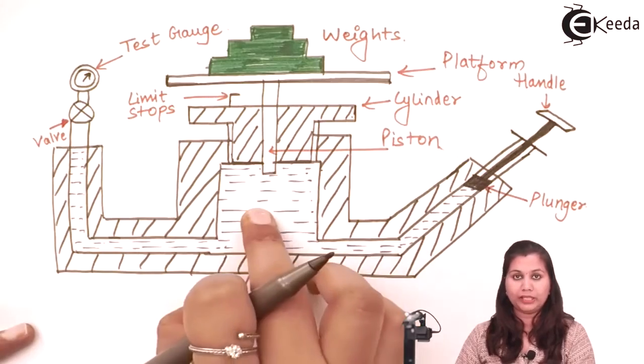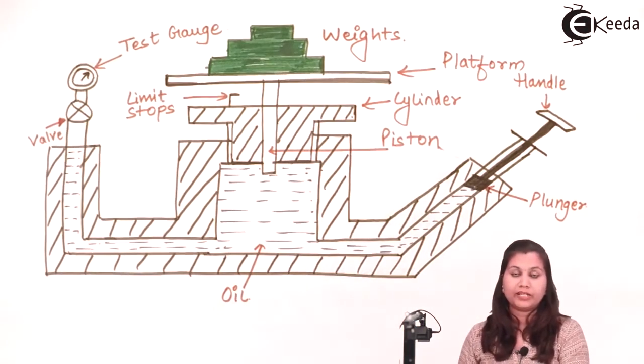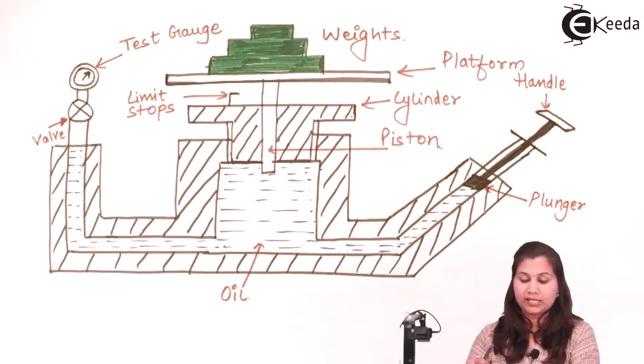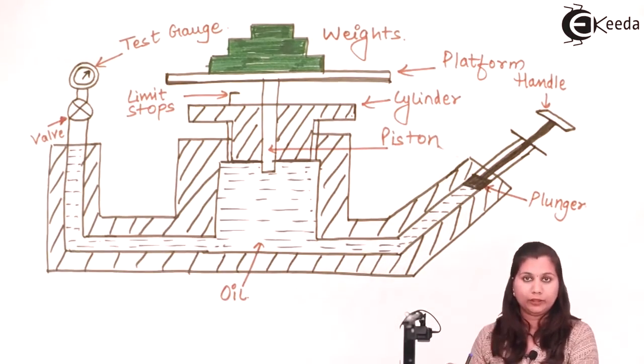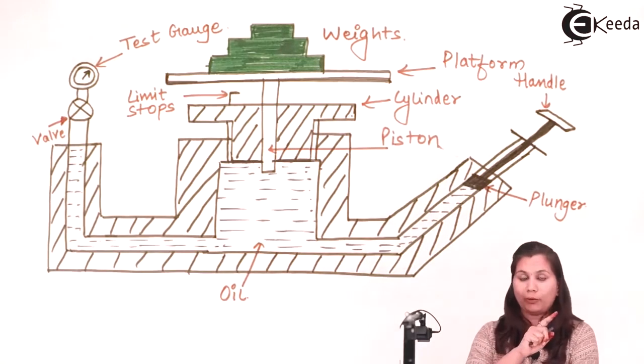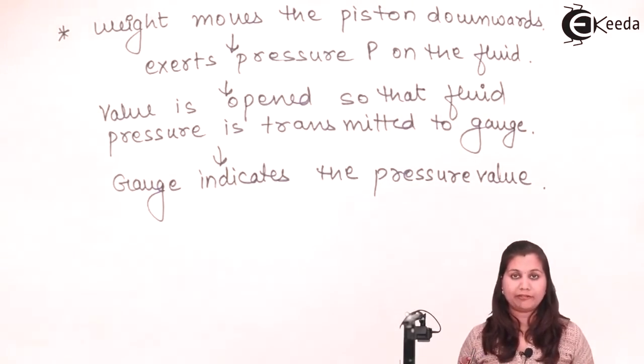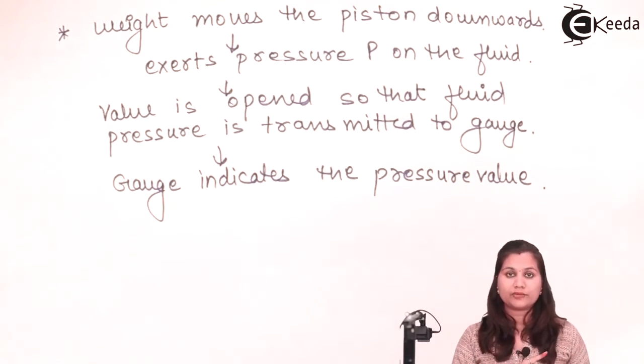Now this fluid pressure has to be equal to the pressure which we have calculated earlier. If it is not equal, then corrections will be made in the test gauge and the readings are made equal. So here you can see that with the help of the known amount of weight, we have kept the same amount of weight in both the measurements, so the same amount of pressure has to be generated. First pressure we have already calculated by using that formula P equals mg plus F divided by A. By using that pressure value, we have seen that the reading of the pressure gauge the second time should be equal to the first value which we have calculated earlier. If it is not equal, then calibrations have to be done, corrections have to be made so that the gauge gives us the correct indications of the pressure.